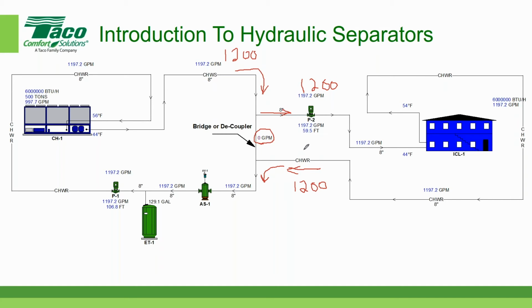It's worth mentioning, even though it may be obvious, because this is a low loss header or a decoupler, the flow across the bridge is 0 gallons per minute. And by default, if you have 0 gallons per minute across this point from here to here, then you meet the requirement of having 0 pressure drop. So that's when our primary flow, we'll put a P over here on the left side, and our secondary flow are equal. That's our second case, second situation.